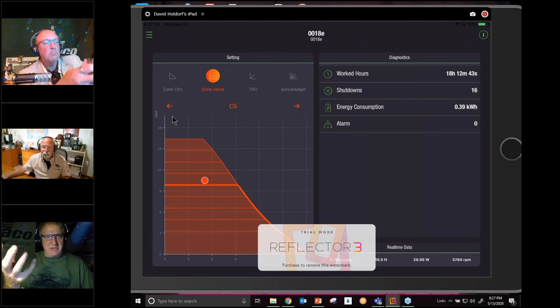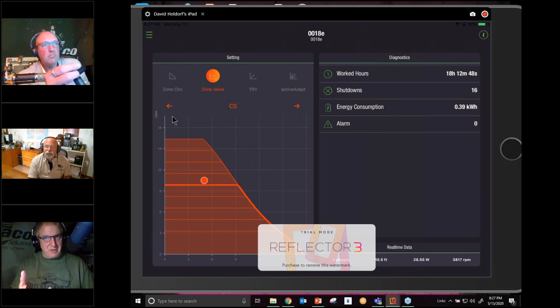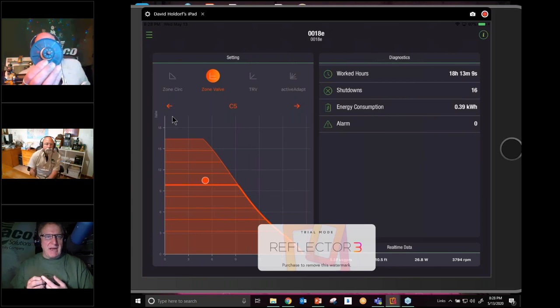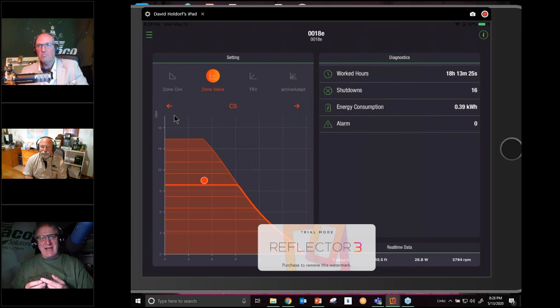Now you've got a permanent always-on magnet in there, and you have water circulating through the pump that also has a lot of black iron oxide, or magnetic crud, in the system. And you want to make sure that you protect that permanent magnet from the magnetic crud. We have two ways of doing that. First, we have what Dave is showing there, called a bio barrier. Bio stands for black iron oxide. It's a brass mesh barrier that will allow water to go in when you first fill up the system. And there's not a constant exchange of fluid after that. That's really not how they work. But that bio barrier is made of brass, and it basically makes that magnet invisible to the magnetic crud that's in the water. So it's not going to be drawn into the inner workings of the circulator. It's just not going to happen.